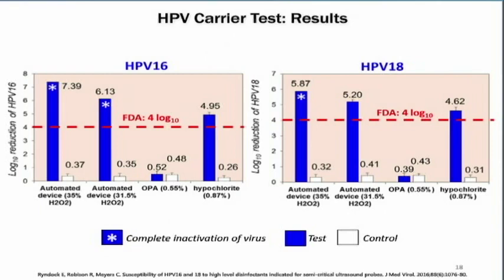So here's results from our carrier test. In these studies, we use both HPV-16 and HPV-18. It's a similar graph as you've seen before, where this is a log 10 reduction of HPV-16 or HPV-18. The blue line shows our tests, and our clear boxes are our control samples, just dried virus that we dried and recovered each time. You can see that in all cases, using this automated device, both using 35% hydrogen peroxide and 31.5% hydrogen peroxide, we exceeded the 4-log reduction that's required by the FDA.